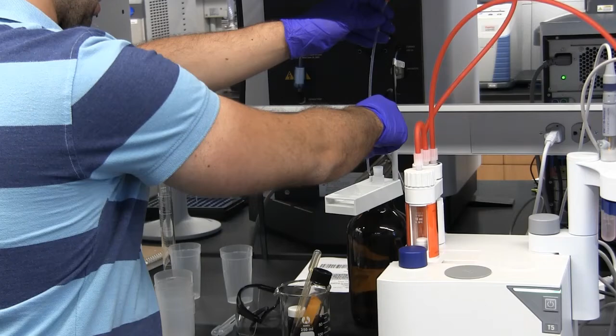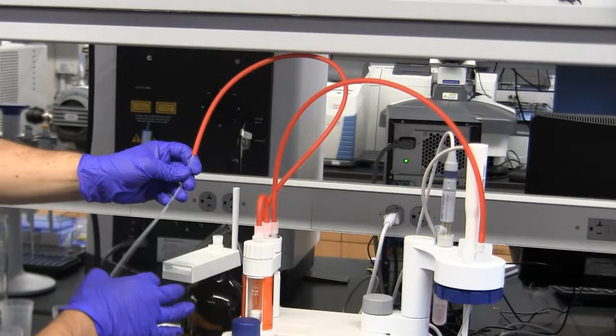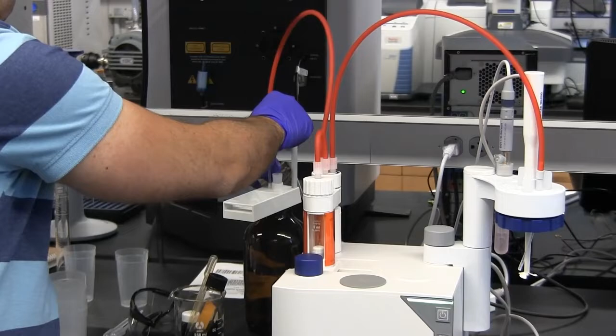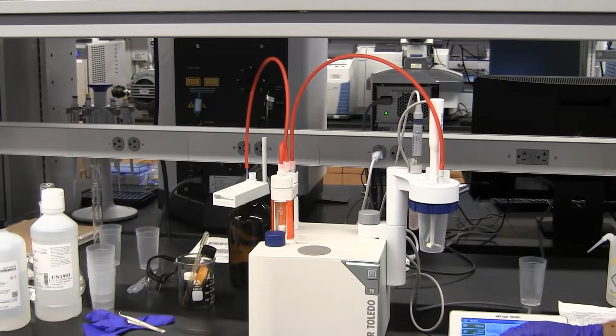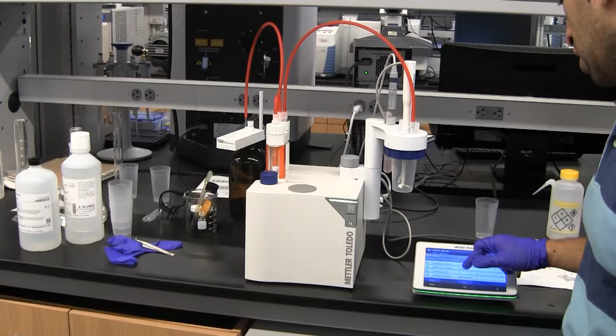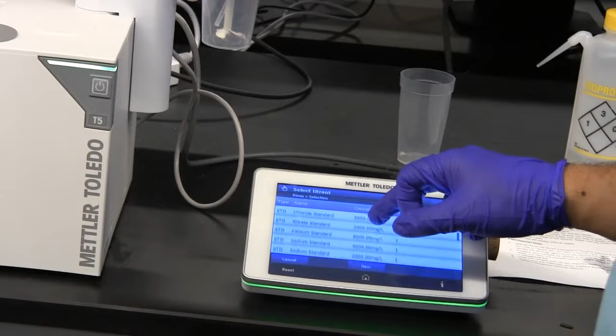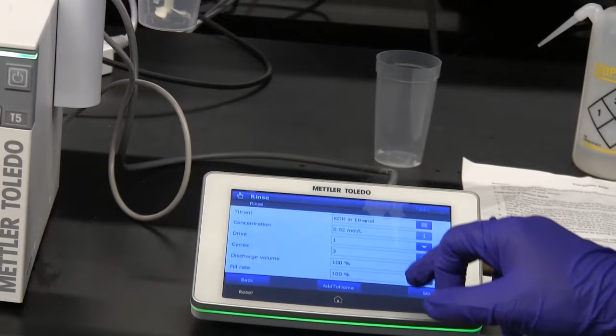So now we will cycle. Make sure also once you put it in here that it goes down to the bottom of the brown bottle, and then we will do a rinse. But before doing a rinse, make sure you have a waste cap connected to your system until it ticks, and then you do a rinse of 3 cycles. Choose the titrant. This time it's KOH, potassium hydroxide in ethanol. Choose this one, 3, and start.